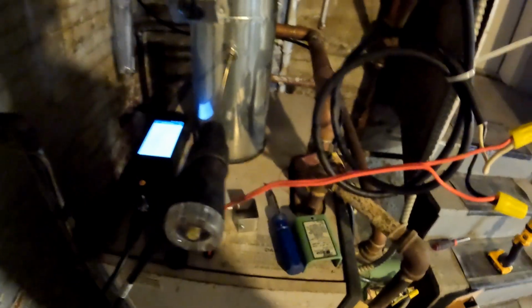Okay, this is the Slant/Fin boiler. This is the completion of the barometric damper. MG1 draft control, 6-inch. Two spill switches, one on the top, one on the bottom. This is modulating to control the draft.